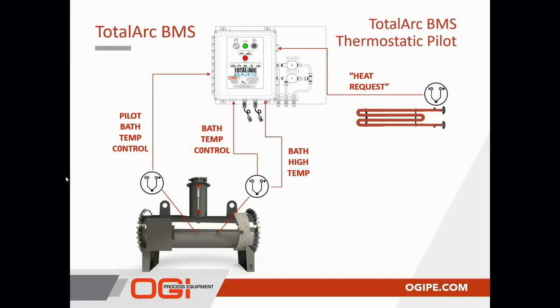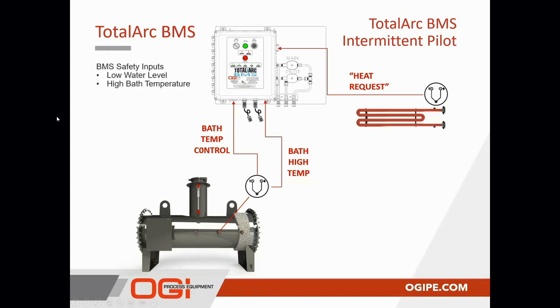In an intermittent pilot configuration, the standard BMS features remain the same. We're still looking at the same BMS safety hardwired limits that are all wired in series, and they will cause a lockout. We're still looking at a loss of pilot after a pilot is proven causing the main burner and the pilot to shut down and a 5-minute post purge to occur prior to relight. So essentially, the BMS really sees no difference between the two. It's just the way that the pilot is being controlled.